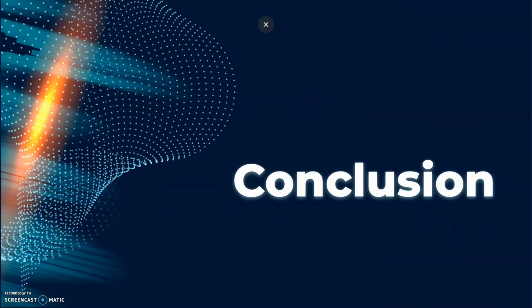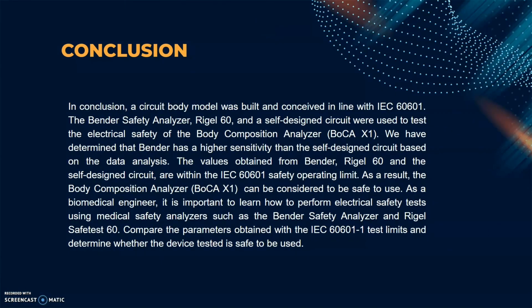Okay, now is for the conclusion. In conclusion, a circuit body model was built in line with IEC 60601. The Bender safety analyzer, Rigel 60, and the self-designed circuit were used to test the electrical safety of the body composition analyzer BOCA X1. We have determined the Bender has higher sensitivity than the self-designed circuit based on the data analysis. The values obtained for the Bender, Rigel 60, and the self-designed circuit are within the IEC 60601 safety operating limits. As a result, the body composition analyzer BOCA X1 can be considered safe to use.